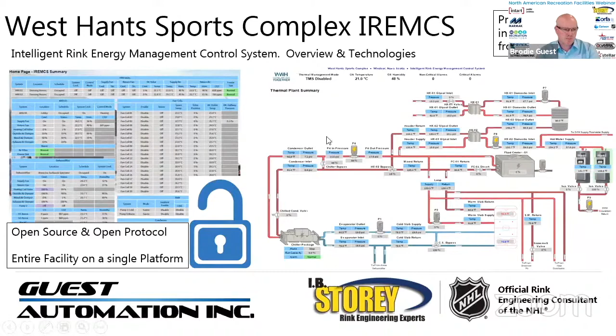I mentioned integration in the past slide, and quite frankly, integration is so important and is the key to success, really. When we look at this floor plan graphic on the left and we see the energy flow of the system, the R on the left stands for the refrigeration and the refrigeration plant itself. From there, we see it carries heating, cooling, and dehumidification to the rink space. Continuing to move to the right, we're heating the common areas, the offices, the meeting rooms, community rooms. And then furthermore, still passing 100% recovered heat to the turf field, which again, extremely efficient.